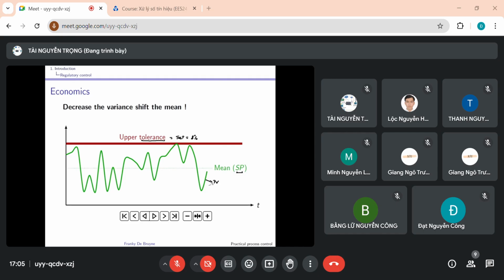So how will he do that? He will look at PV, previous PVs coming from the past, and he will look at the 3 sigma value, and he will set his set point as follows. It will be the upper tolerance minus 3 times the sigma on PV. He has had a course on statistics in the past, and he knows that in 99% of the cases the PV will remain below the upper tolerance if the production process is running in a normal fashion.